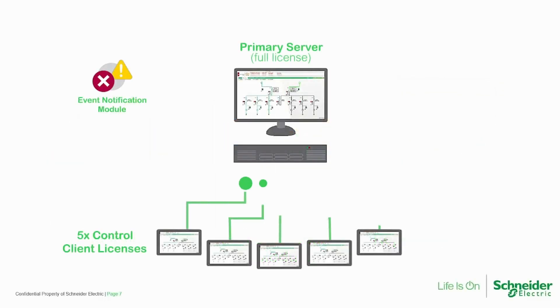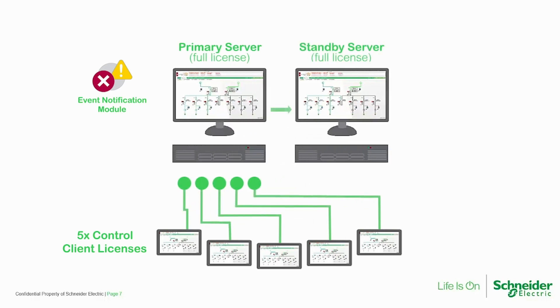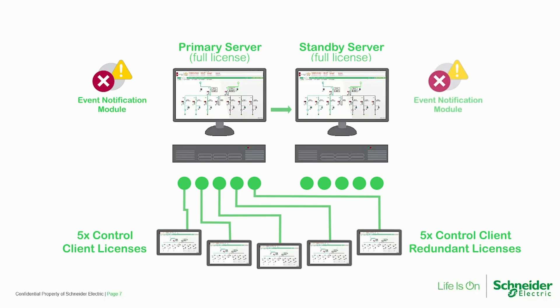Finally, a redundant system adds a bit of complexity. The standby server must have a full server license with the same number of points as the primary server. However, clients only require a redundant client license, which always has unlimited points. The number of redundant client licenses should still match the primary server. If you have purchased the event notification module, you'll want a second module license to run on the standby server as well.